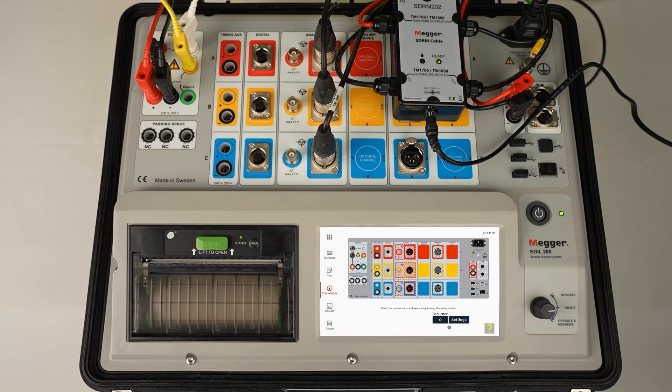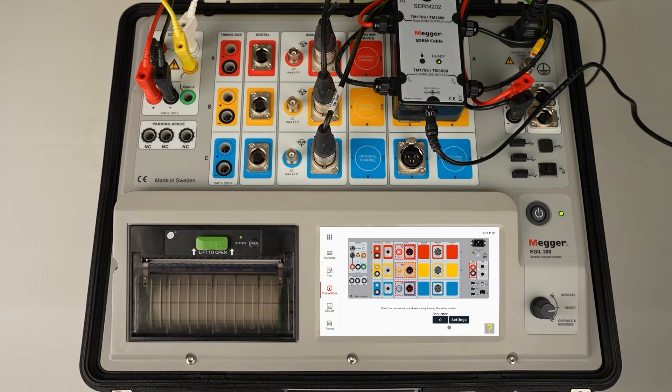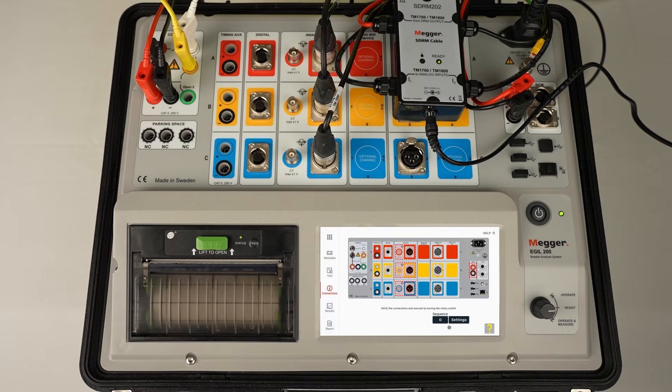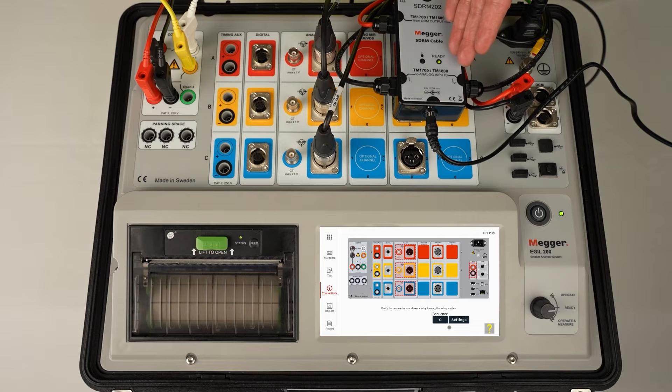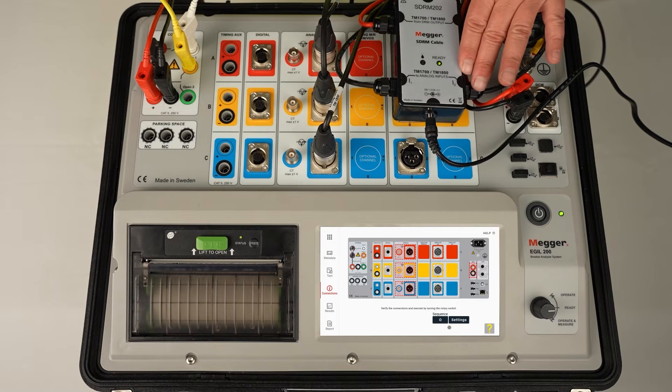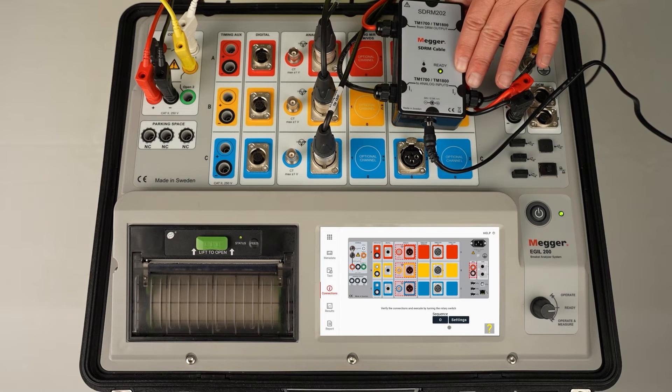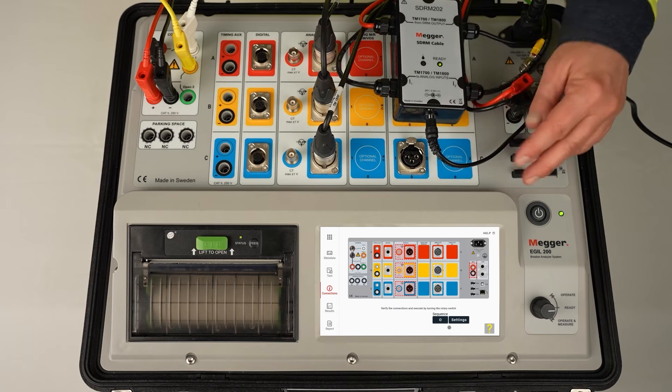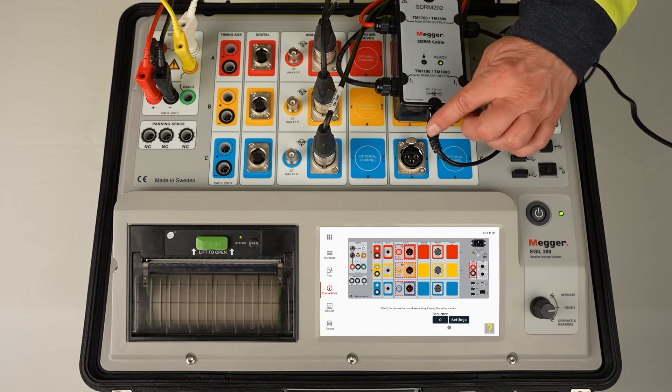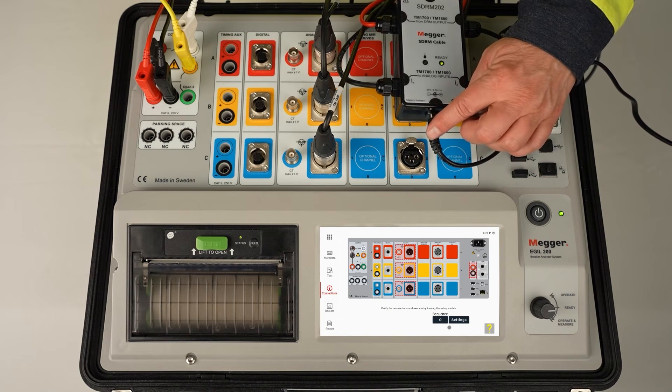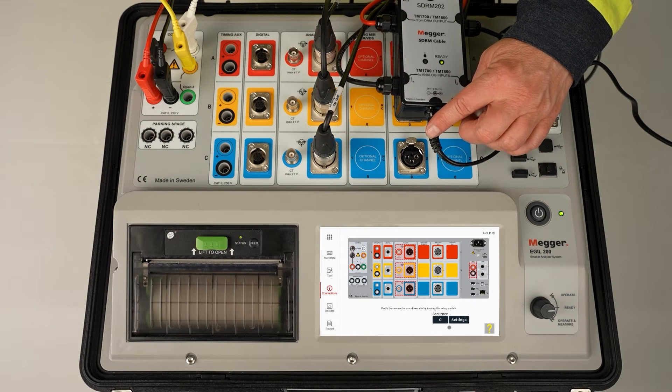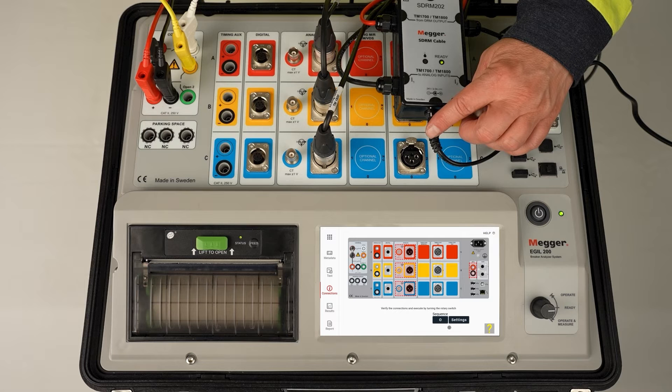The SDRM box needs to charge. It takes a few seconds between each shot, but the first time it takes about two minutes. As you see, now when we've done the connection, it's already ready. And don't forget, it needs to have the charging connected all the time. When it's ready, we can do the measurement and turn the knob.